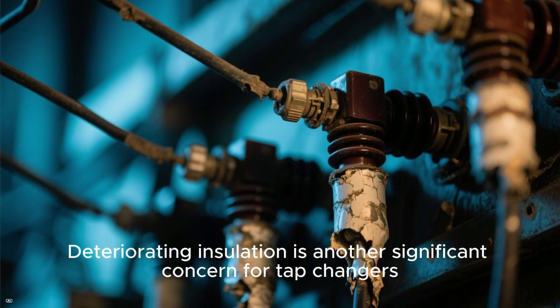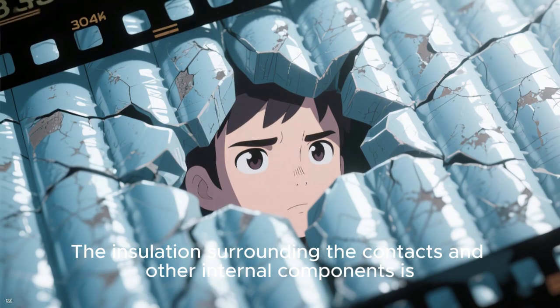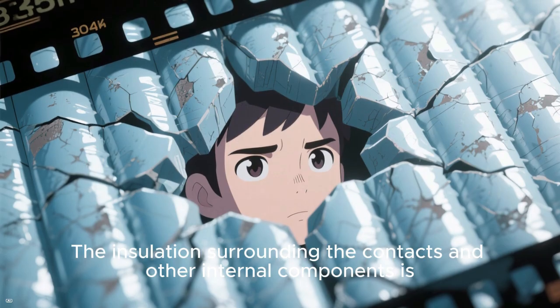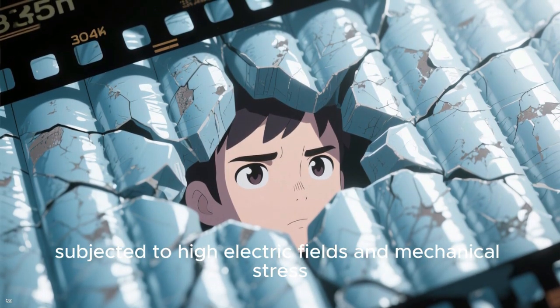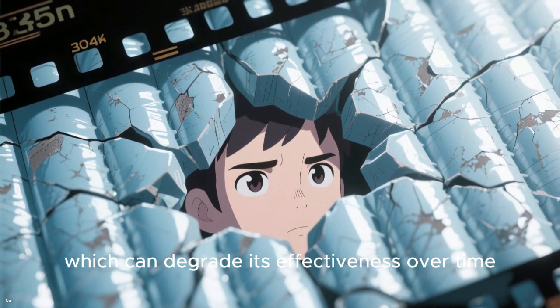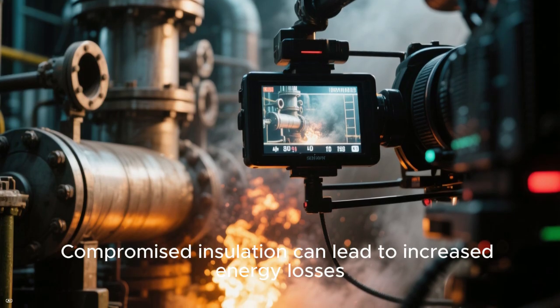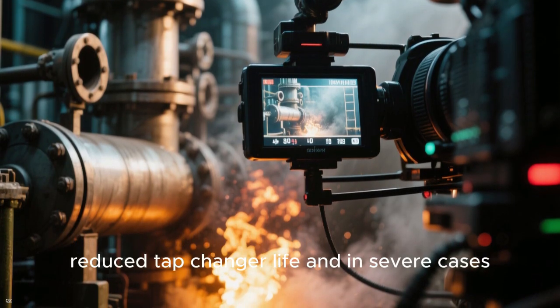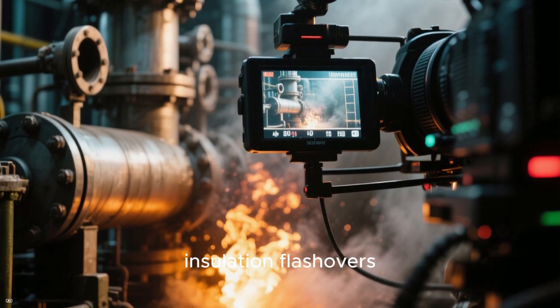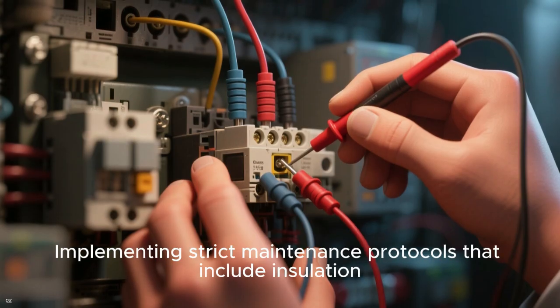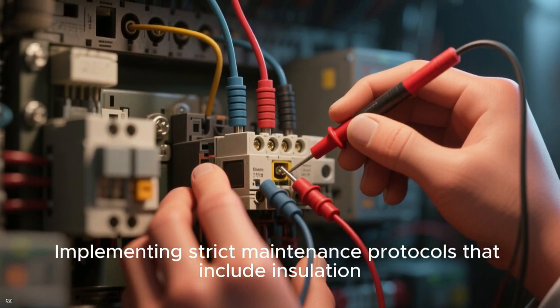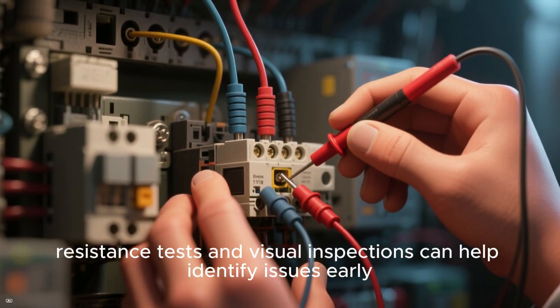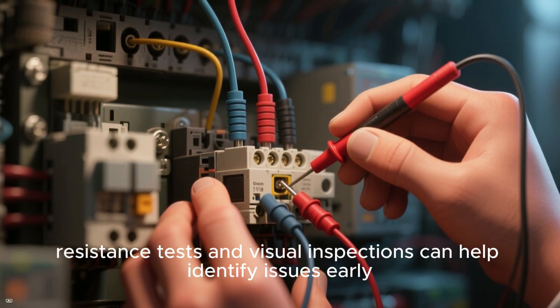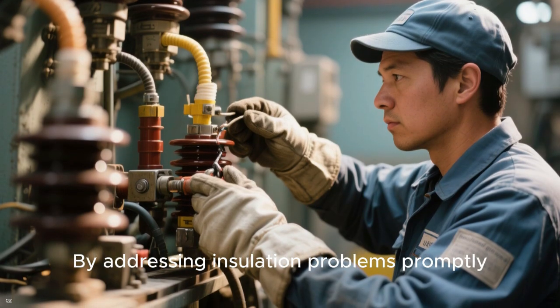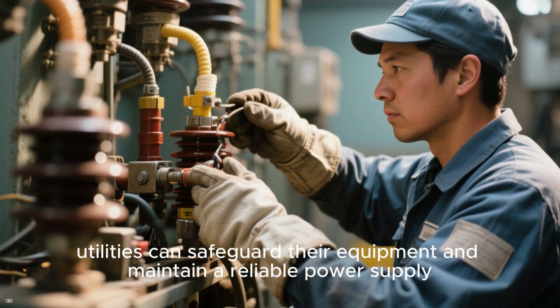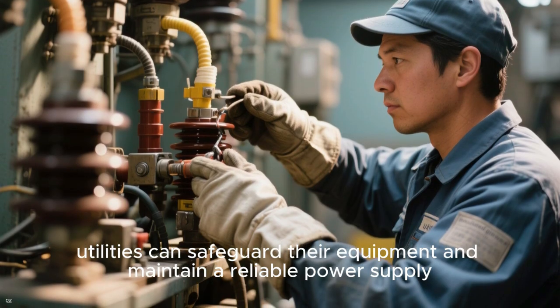Deteriorating insulation is another significant concern for tap changers. The insulation surrounding the contacts and other internal components is subjected to high electric fields and mechanical stress, which can degrade its effectiveness over time. Compromised insulation can lead to increased energy losses, reduced tap changer life, and in severe cases, insulation flashovers. Implementing strict maintenance protocols that include insulation resistance tests and visual inspections can help identify issues early. By addressing insulation problems promptly, such as through cleaning or replacement, utilities can safeguard their equipment and maintain a reliable power supply.